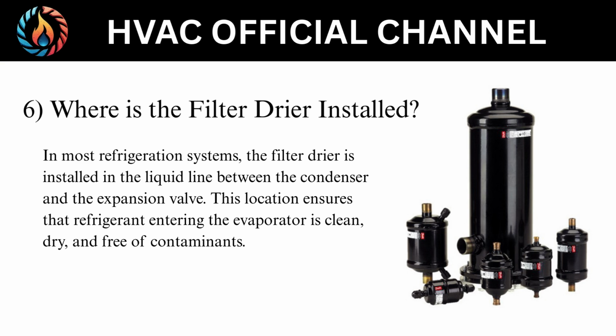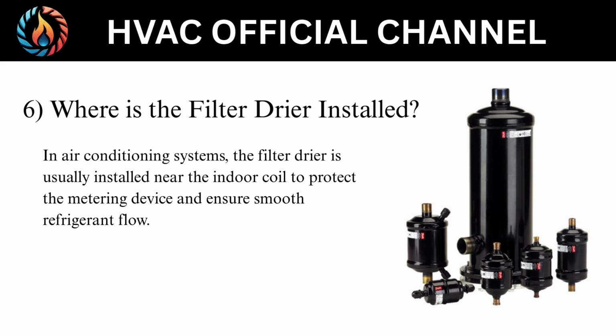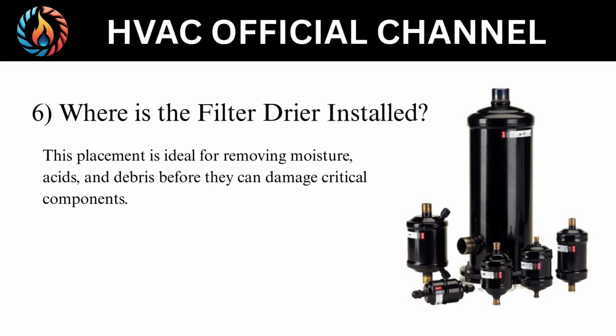6. Where is the filter dryer installed? In most refrigeration systems, the filter dryer is installed in the liquid line between the condenser and the expansion valve. This location ensures that refrigerant entering the evaporator is clean, dry, and free of contaminants. In air conditioning systems, the filter dryer is usually installed near the indoor coil to protect the metering device and ensure smooth refrigerant flow. This placement is ideal for removing moisture, acids, and debris before they can damage critical components.